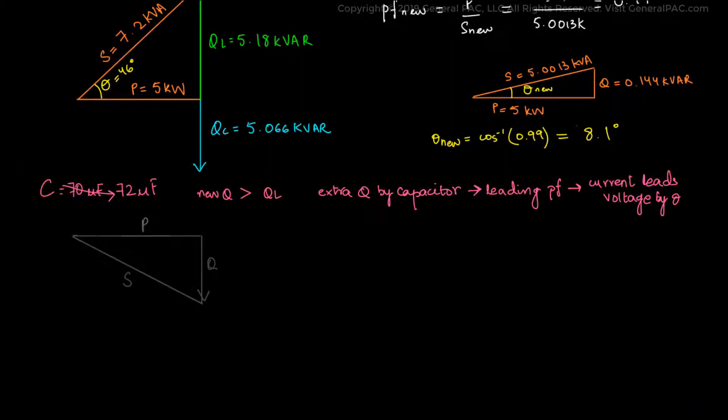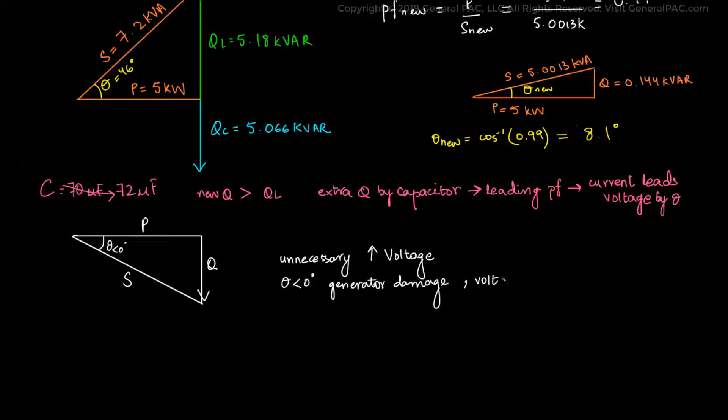Something to keep in mind is that a leading power factor can in fact cause additional problems in the power system, such as unnecessary rise in the system voltage. The negative phase angle becomes dangerous for sensitive equipment and even possibly damaging to generators, whose voltage regulators will not be able to handle the spontaneous change in the system voltage and fail to adjust accordingly. Now, we will discuss generator protection in future topics. With that being said, we will now conclude the introduction to power factor series.